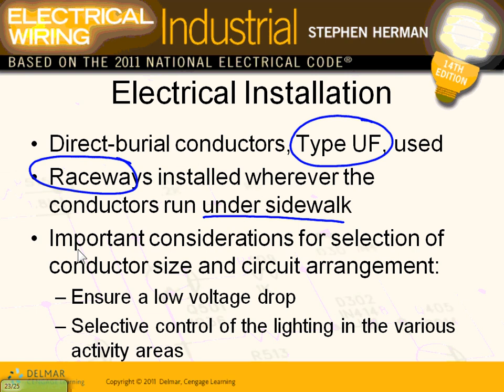When I redline your power and site plan, I'm going to ask what type of conductor you used outside. If you said number 12, you have no idea what parking lot powering is. You can't use number 12 outdoors — at least you need number 10. At least, when you get outside the building for a parking lot, use number 10. Bigger parking lots go in the aughts — 1-aught, 2-aught, 3-aughts — even though the load on them is only 20 or 30 amps. The reason: voltage drop, because you're going longer distances outdoors.